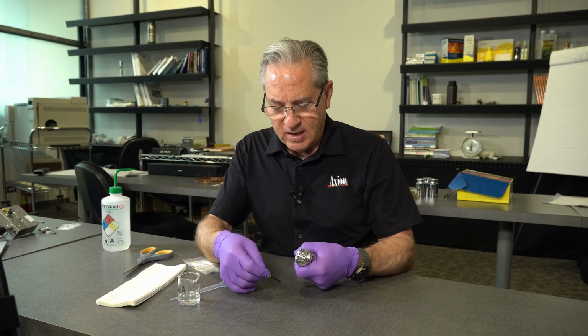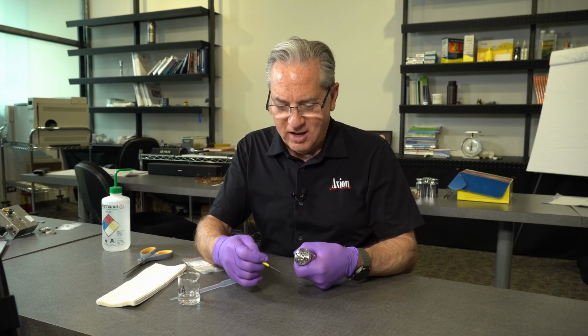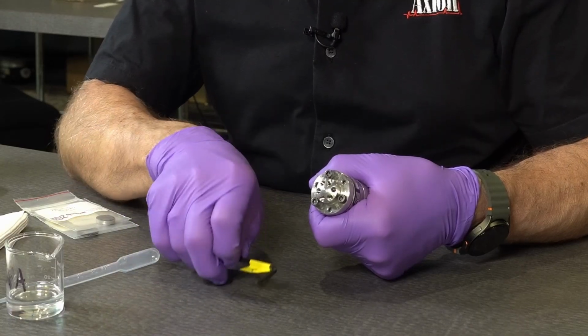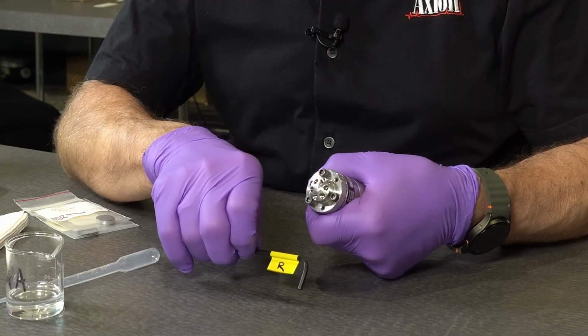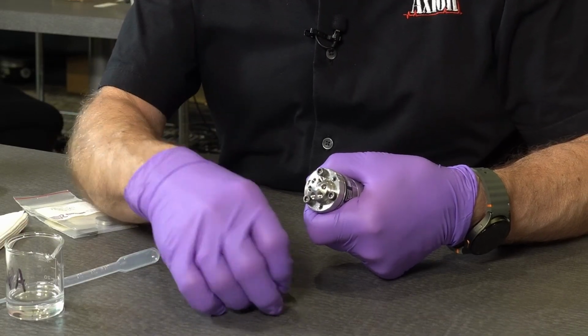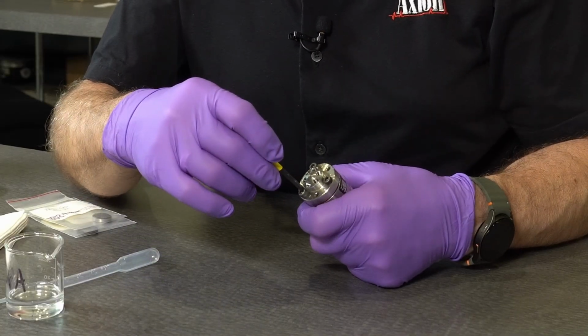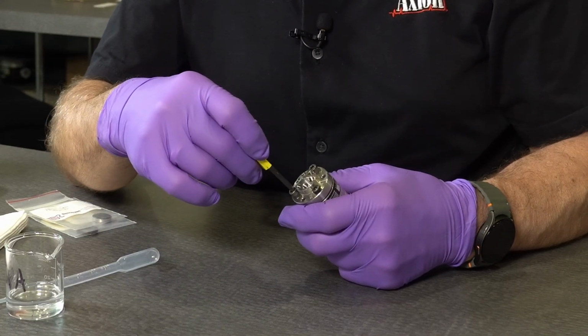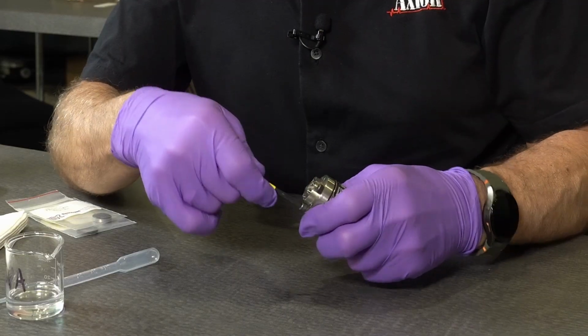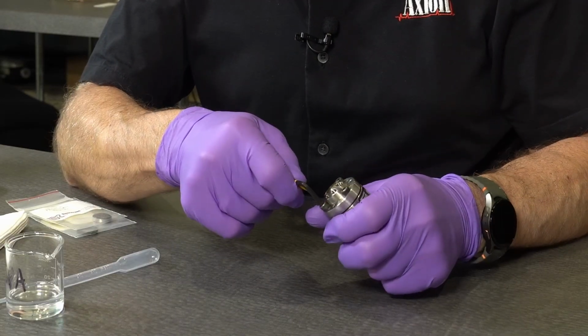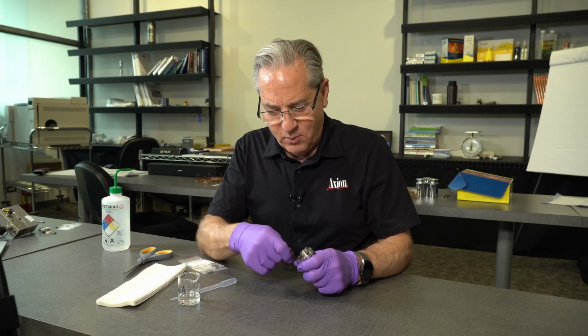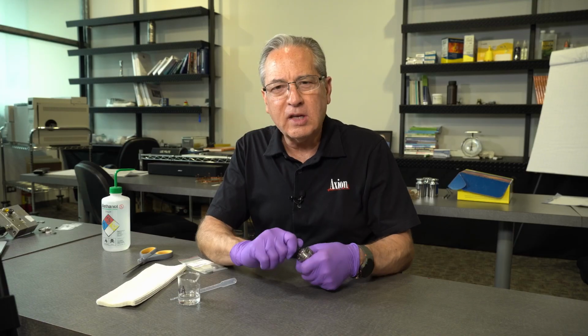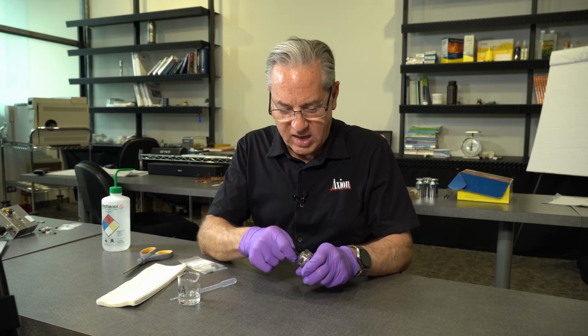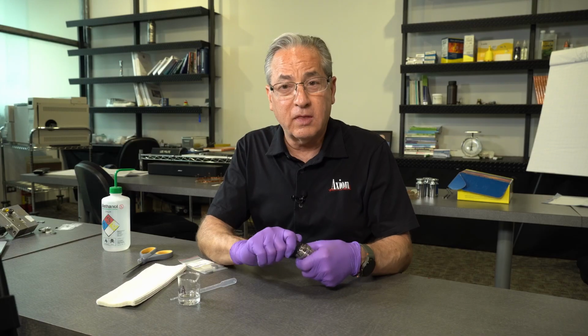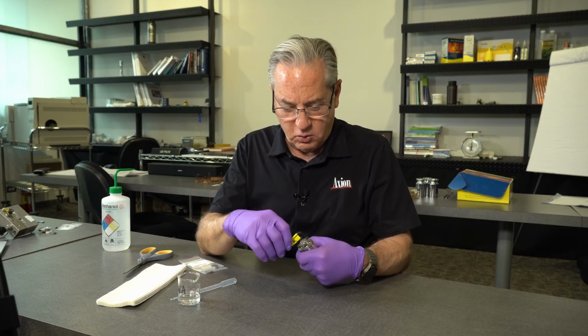So I have you get an Allen wrench, and mine is labeled. How do I have mine labeled? It's labeled R for Rheodyne, because how many times have you reached in the drawer and tried the 20 wrenches only to find that the right one is in your pocket? So this one we have labeled. So what we want to do is loosen these 3 hex nuts, and back in the day, we would actually have torque settings for them, and we talked about the higher torque you set on them, the higher pressure the valve can withstand, but the sooner you're going to start to wear out the rotor seal.